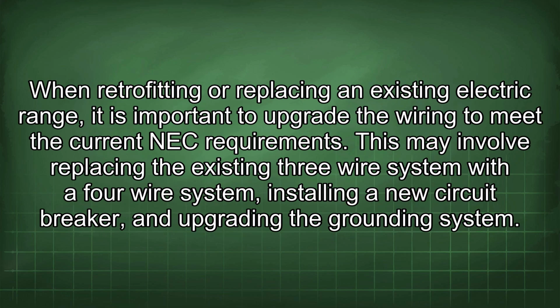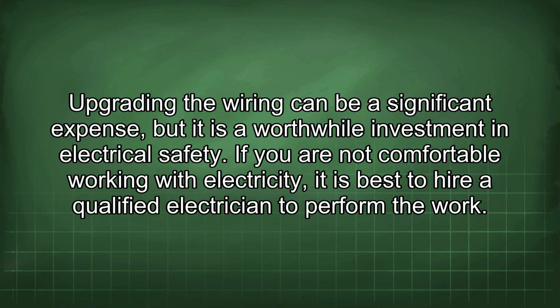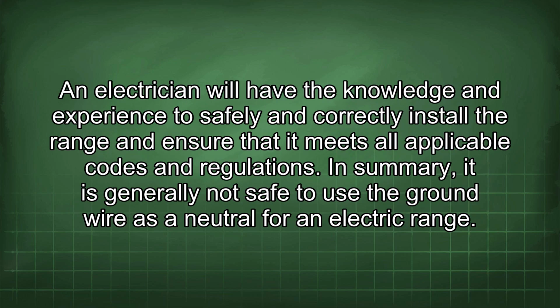When retrofitting or replacing an existing electric range, it is important to upgrade the wiring to meet the current NEC requirements. This may involve replacing the existing 3-wire system with a 4-wire system, installing a new circuit breaker, and upgrading the grounding system. Upgrading the wiring can be a significant expense, but it is a worthwhile investment in electrical safety. If you are not comfortable working with electricity, it is best to hire a qualified electrician to perform the work. An electrician will have the knowledge and experience to safely and correctly install the range and ensure that it meets all applicable codes and regulations.